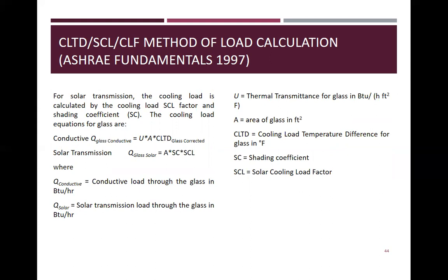Q solar is the solar transmission load through the glass in BTU per hour. U is the thermal transmittance for glass in BTU per hour square foot Fahrenheit. A is the area of glass in square feet. CLTD is the cooling load temperature difference for glass in Fahrenheit. SC is the shading coefficient. SCL is the solar cooling load factor.